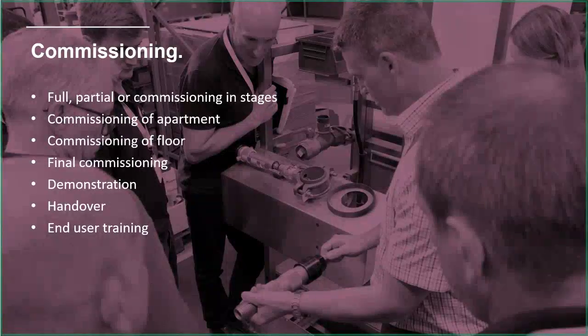So obviously their commissioning would be concentrating on the works that they've done, and then it'll be up to another sprinkler contractor or multiple sprinkler contractors to come in and do the final bit from the zone valve to fit out the shop unit or the floor, and their commissioning would be concentrating on the bit that they've done. That's all fair. You shouldn't be taking responsibility for works that you haven't done. So commissioning is focusing on the works that you have done. So that's an example there of full, partial, and commissioning in stages.